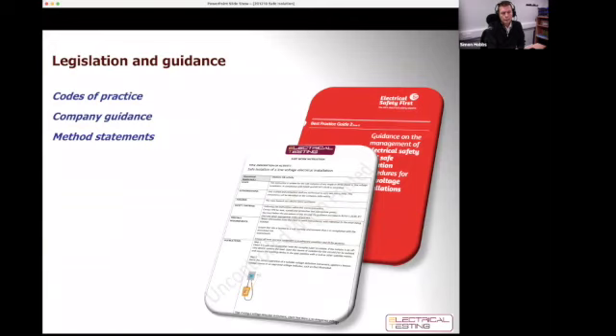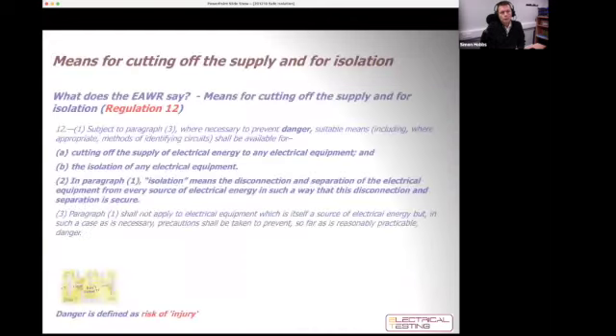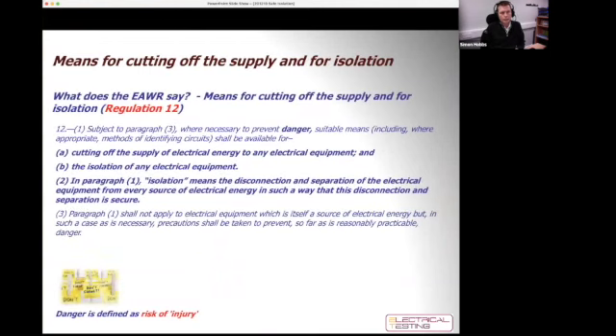So let's have a little drill quickly into what the law says about isolation. What does the Electricity at Work Regulations say? Regulation 12 says it is a means for cutting off the supply and for isolation. Just to read through the first couple of sentences here: subject to paragraph 3, which is when we have a piece of equipment that generates its own energy, where necessary to prevent danger, or let's say a risk of injury, suitable means, including where appropriate identifying circuits, shall be available.